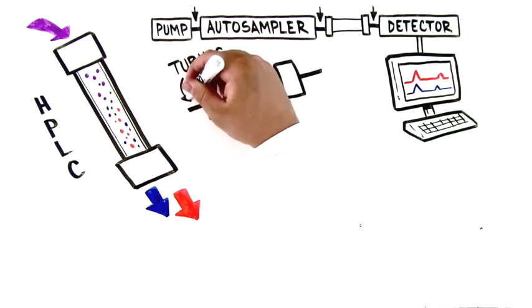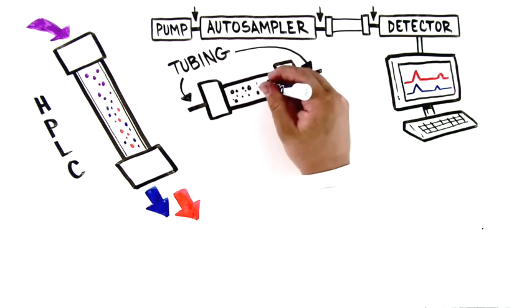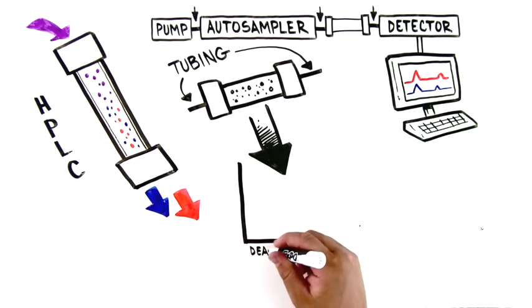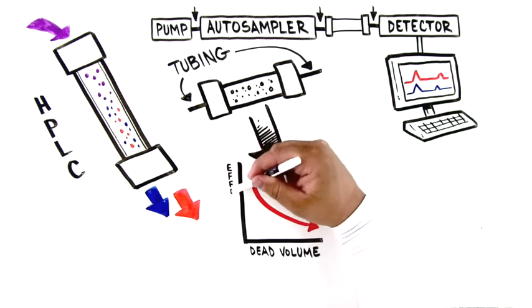The tubing before and especially behind the column strongly affect the quality of chromatographic separations because every additional dead volume can significantly decrease the efficiency.